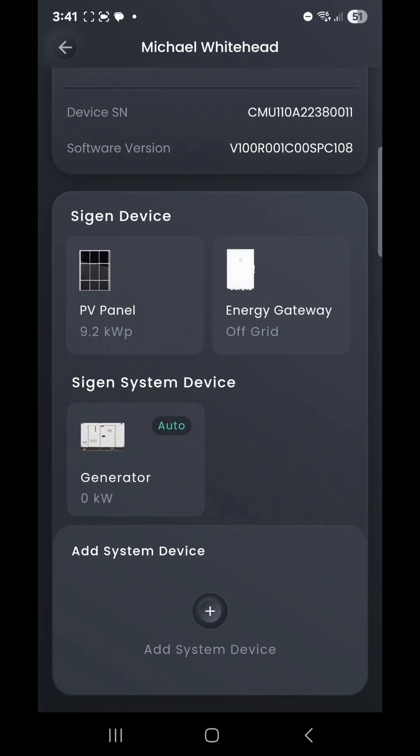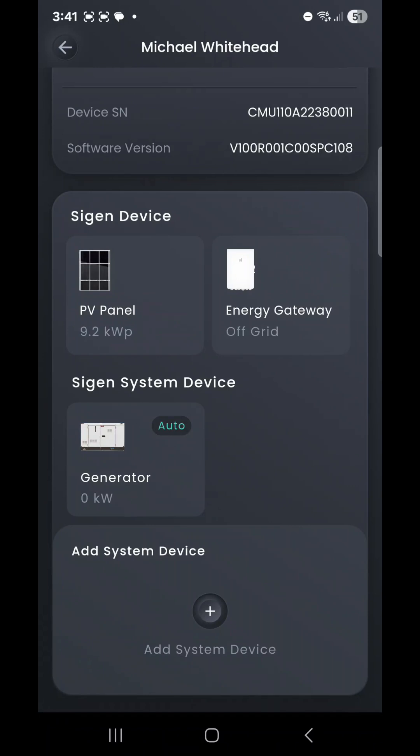This utilizes a two-wire start trigger into your automatically operated generator, which allows the SigenStor system to call the generator if it needs help charging the battery system. This happens if the solar is underperforming during extended poor weather conditions, or if you consume more power through the night than normal and your battery capacity is restricted.